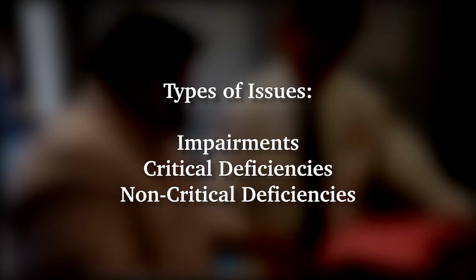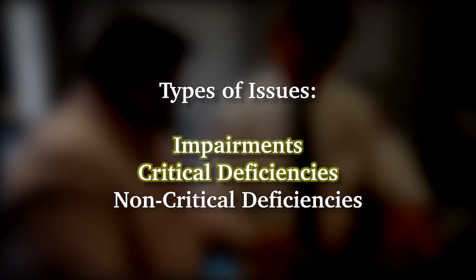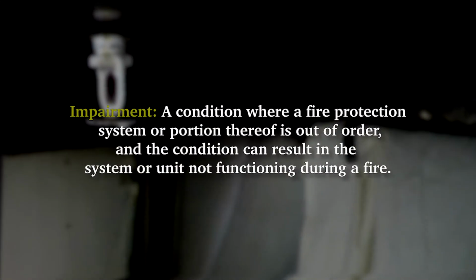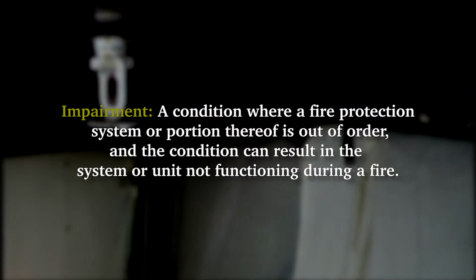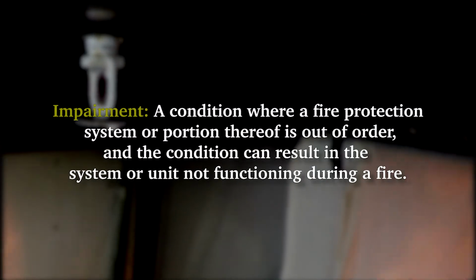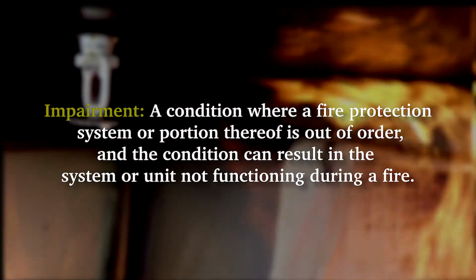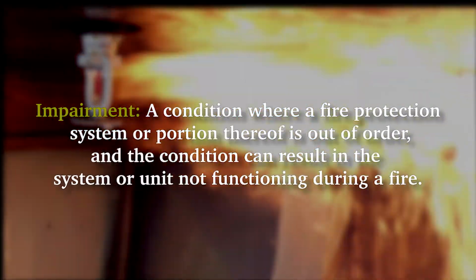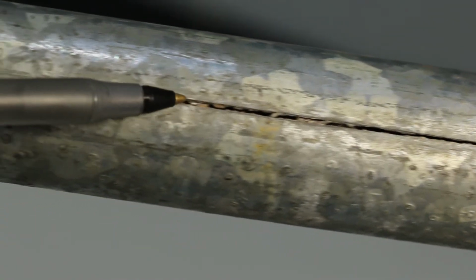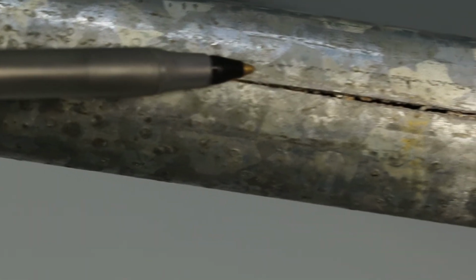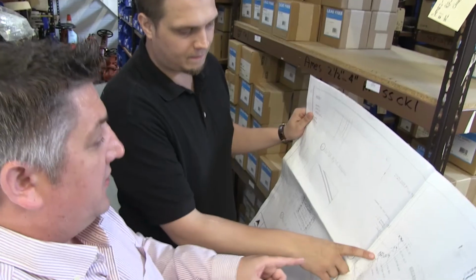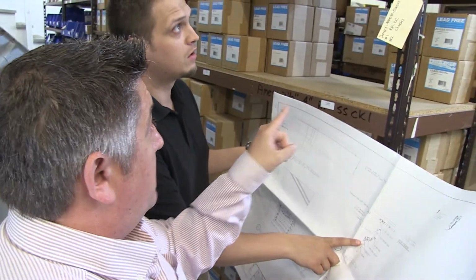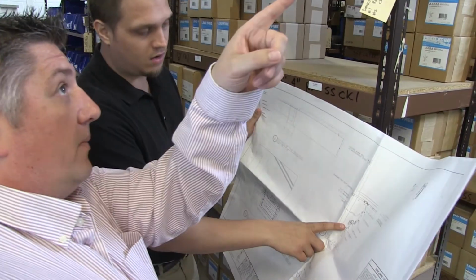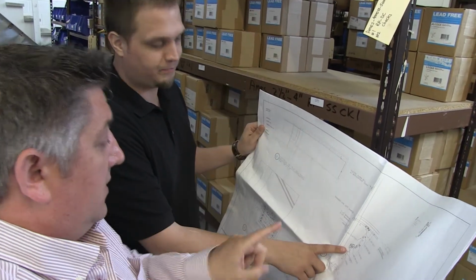When conducting ITM, there are 3 types of issues you may see in a system: impairments, critical deficiencies, and non-critical deficiencies. An impairment is defined as a condition where a fire protection system or portion thereof is out of order, and the condition can result in the system or unit not functioning during a fire. An emergency impairment is due to an unplanned occurrence or was discovered during ITM activities, whereas a pre-planned impairment is due to work planned in advance, such as revisions to water supply or sprinkler system piping.